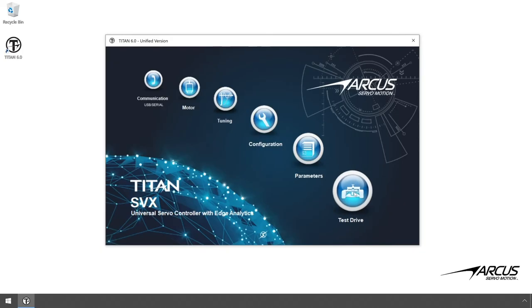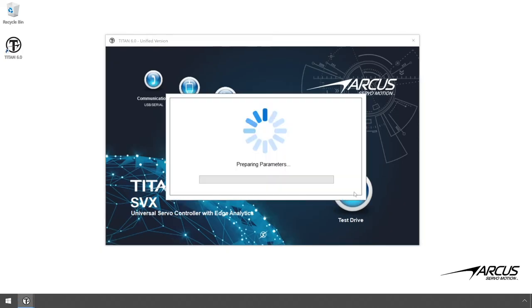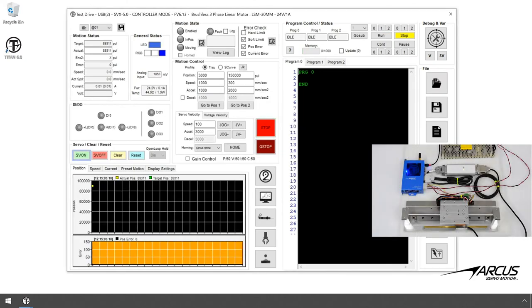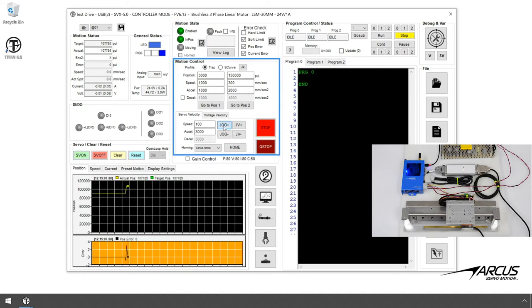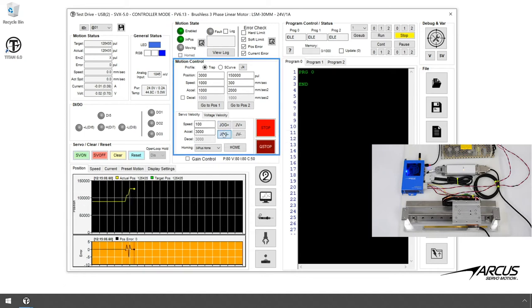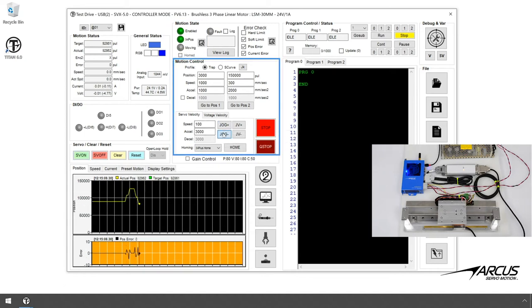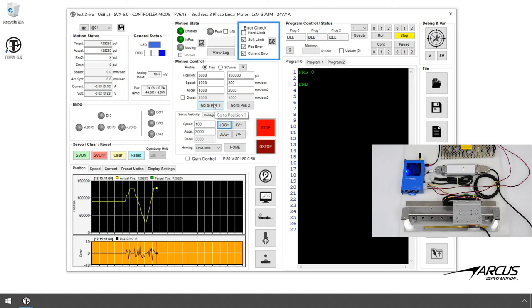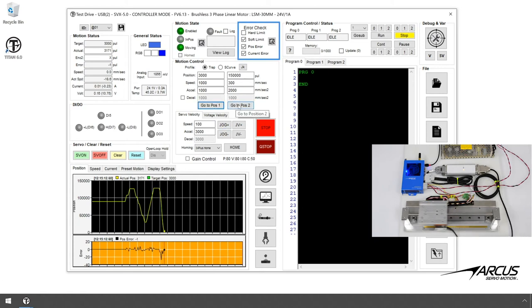Now we will test motion of the motor from the test drive window. To test motion, first enable the motor. You can see that the motor is enabled and in position. Here you can try different jogging or position moves to test the motion of the motor. Note that the soft limits are enabled from the previous detection routine.